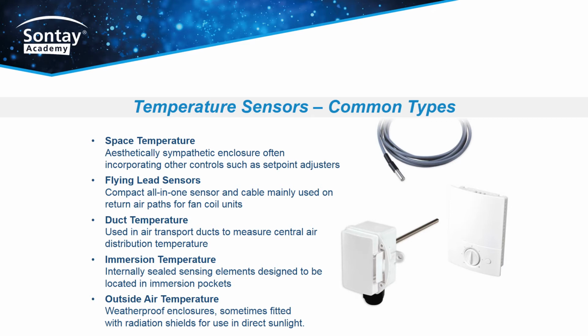Better results will always be achieved by using a space temperature sensor located at the correct height in small spaces, such as partitioned offices. Different temperature sensor types have different responses. RTDs tend to provide a faster response to temperature changes than thermistors, but are usually more expensive. If the application requires a fast response, it is important to select an appropriate sensor type.